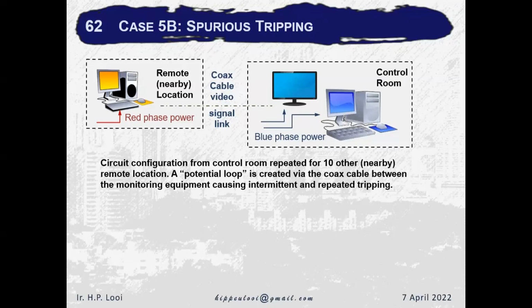It still didn't work. Finally, they called me and we troubleshot, and this is what we found. We had a control room, and they were linked through, because the video monitor must be linked. What we found was that the red phase and the blue phase were mixed, so we changed it back to the blue phase and the problem disappeared. But we actually have another case, not a karaoke lounge but something similar. You have a communication potential loop, which can cause this problem.